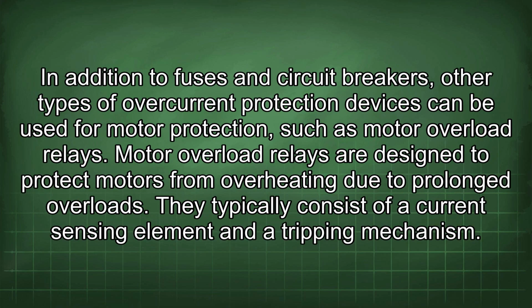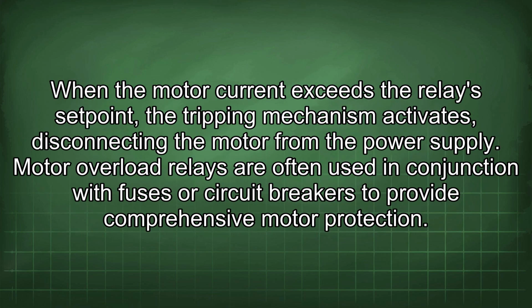In addition to fuses and circuit breakers, other types of overcurrent protection devices can be used for motor protection, such as motor overload relays. Motor overload relays are designed to protect motors from overheating due to prolonged overloads. They typically consist of a current sensing element and a tripping mechanism. When the motor current exceeds the relay set point, the tripping mechanism activates, disconnecting the motor from the power supply.